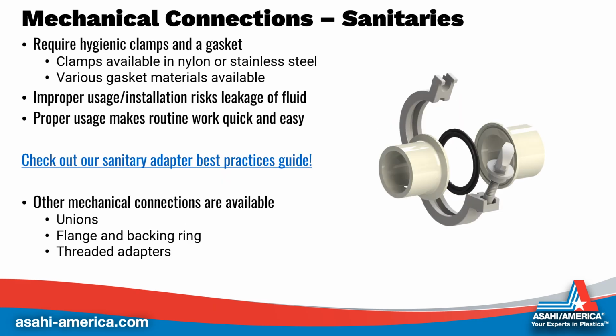Besides welding, PolyPure can be joined via multiple types of mechanical connections. One such mechanical connection is the sanitary adapter. Routine work such as cleaning and sterilization can be done much more easily with a properly installed sanitary adapter. Clamps are available in nylon or stainless steel. The most common gasket materials are EPDM or FKM, but other materials are available upon request. Please visit our website to take a look at our best practices guide for installing sanitary adapters. We also offer additional mechanical connections with the PolyPure line, including unions and standard flange adapters.